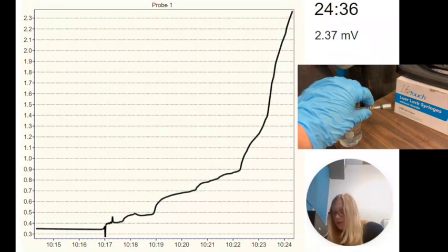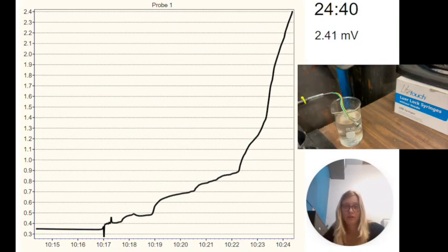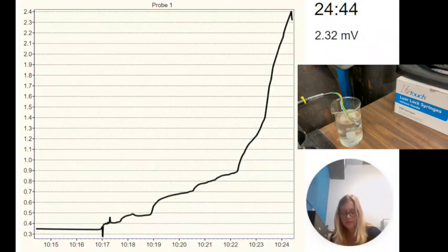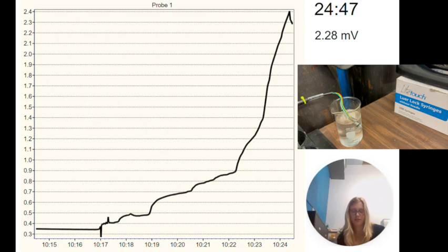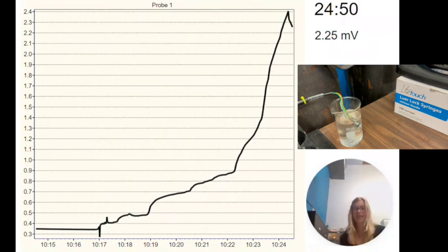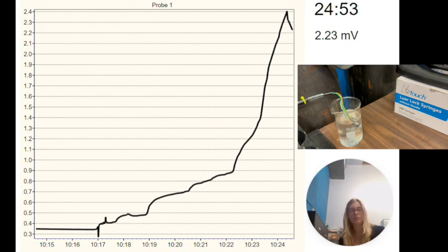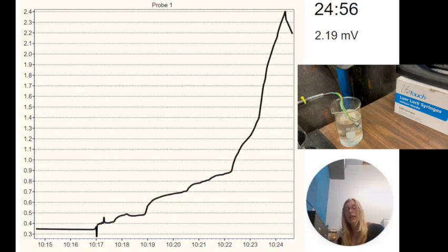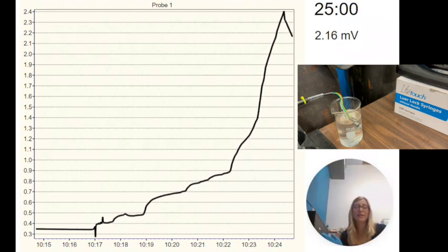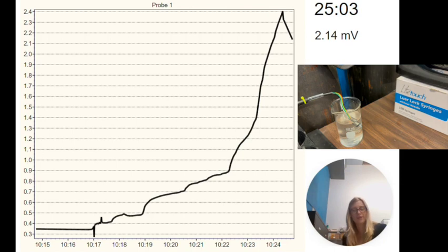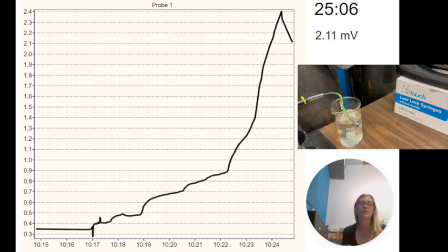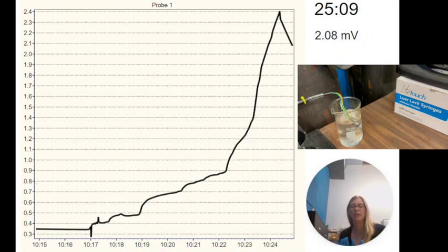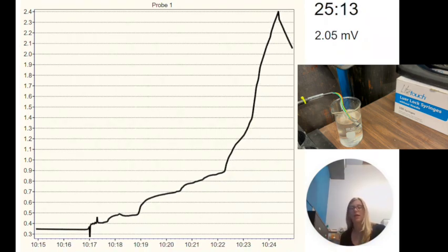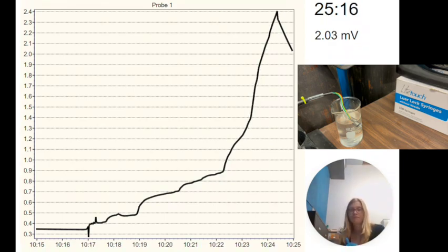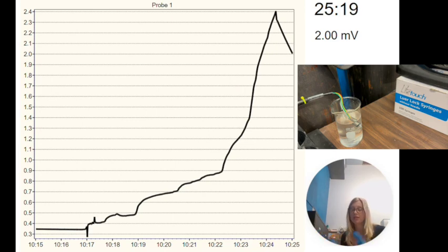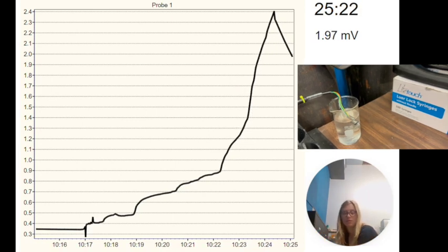Okay, so this sensor finally reached its end voltage at 24:35. So that's way longer than the 3 minutes that we would like it to climb that much. So this sensor would be marked as slow. Likewise, if it now takes over 30 minutes for it to rehydrate back down 1 millivolt, we would also call that slow. So these sensors aren't broken completely. There is a method that you can use to recover them, and I'll show you what that looks like. But let's just wait for it to recover back down, just to see how long it takes.